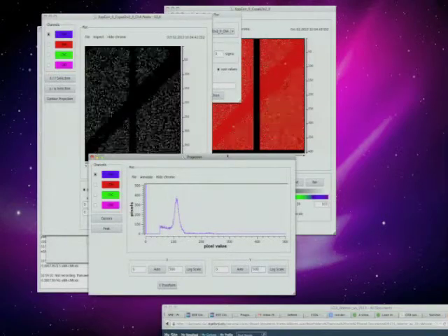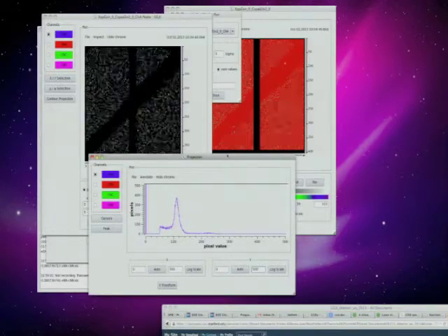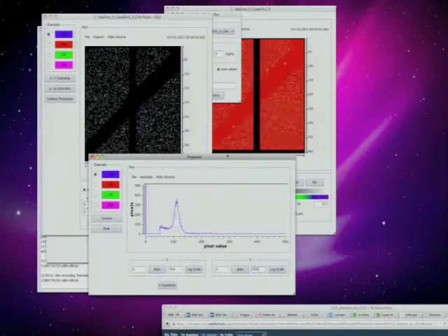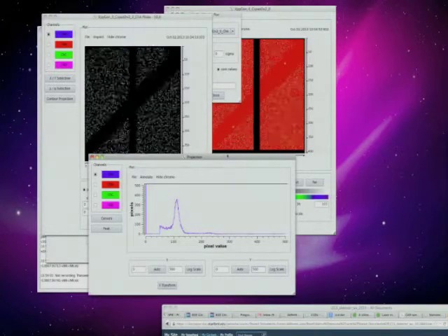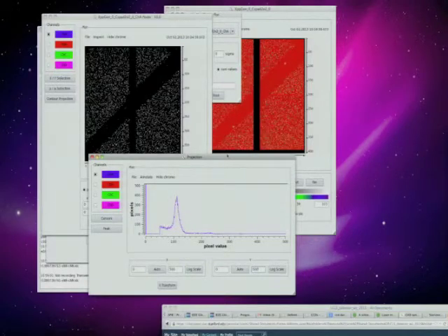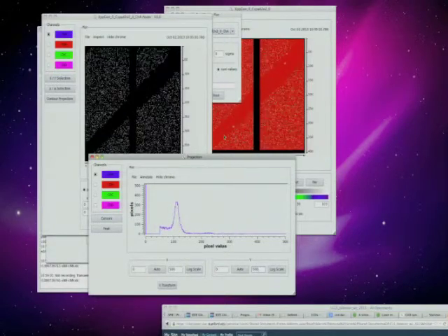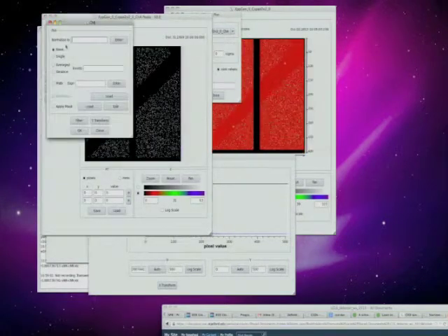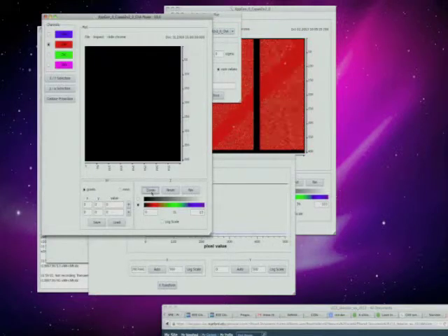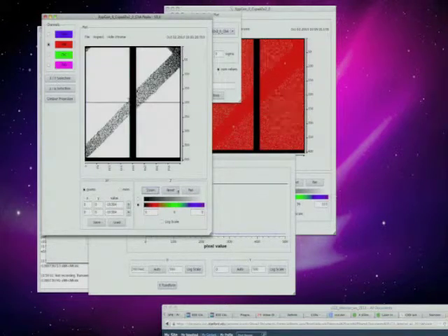And here you see that I made this hard cut at 50, but then up from that, I get, again, all the analog values. The information is completely retained. That's very advantageous because I can basically now make an analog averaging, but I'm cutting out the noise floor. And therefore, especially when one has so few photons, your convergence, your signal-to-noise ratio, which you get after a couple of images, is getting better because you sort of combine the noiseless behavior of a photon counter with the analog behavior of an integrator. Here it is.